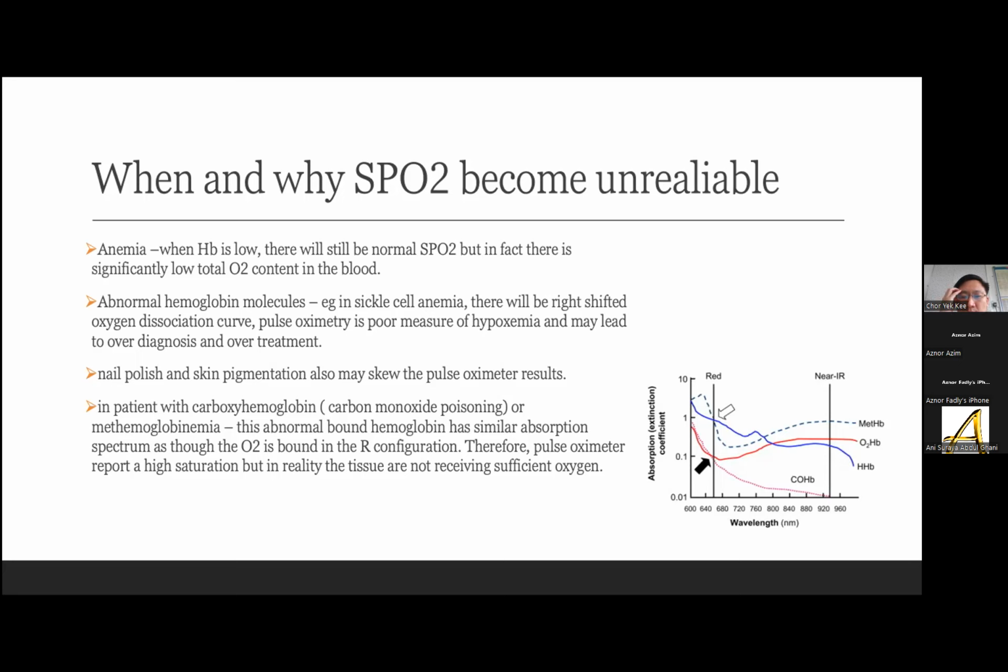So supposedly the child has a normal SpO2, but the SpO2 displayed on the monitor is 5% lower. But newer pulse oximeters have improved a lot. Even a very dark nail polish, or the brownish one that people use, will only drop the SpO2 by around 2 to 3%.